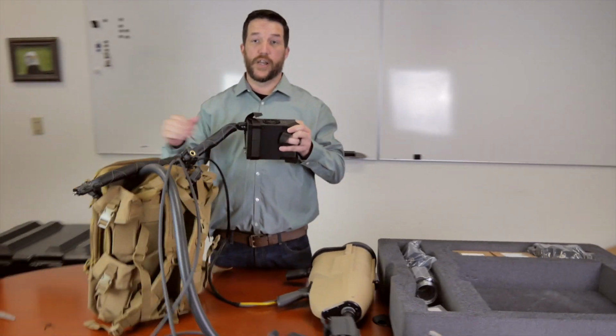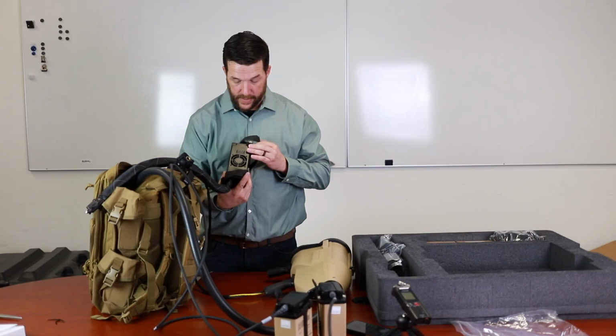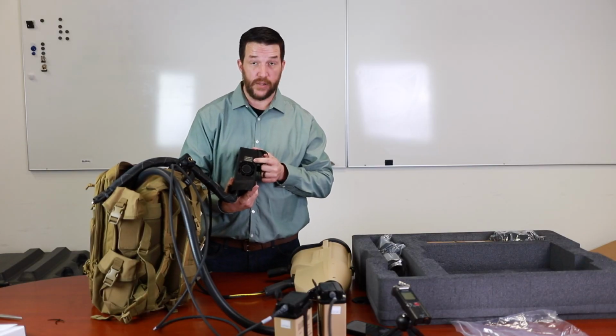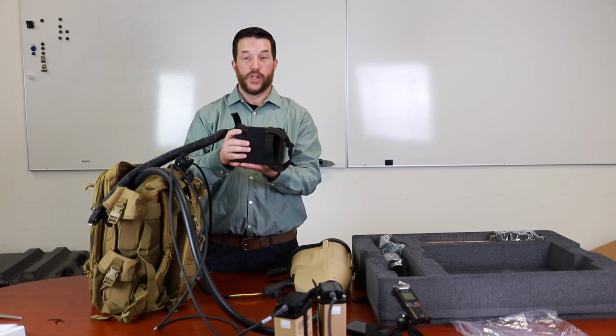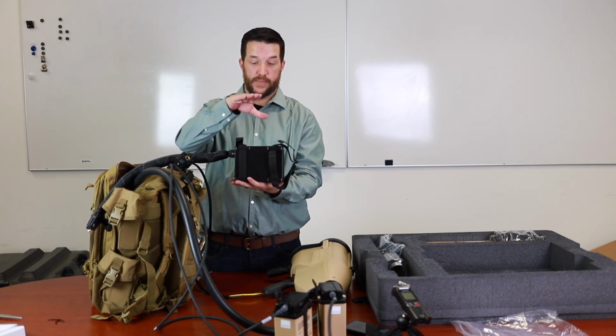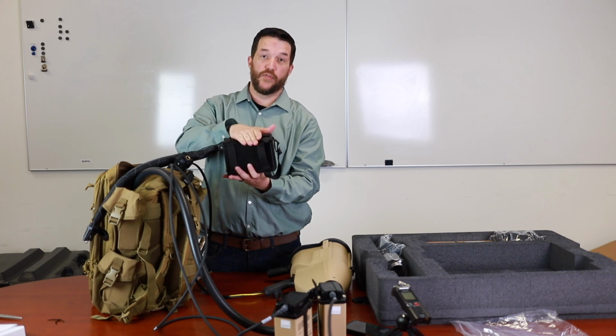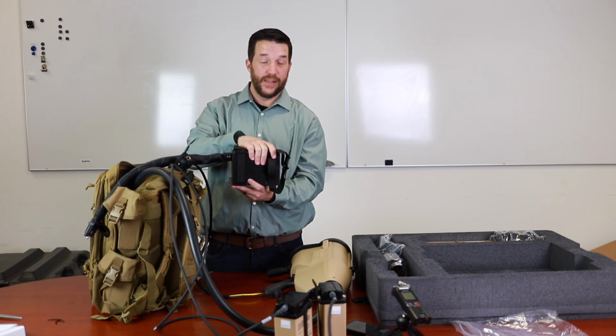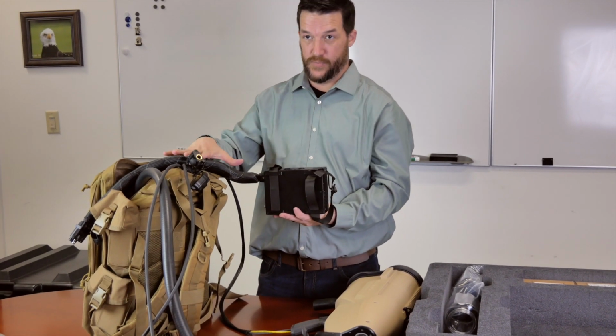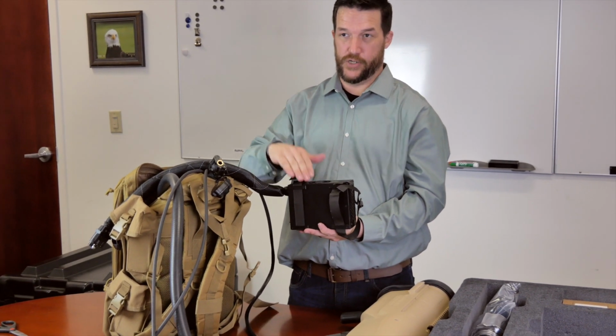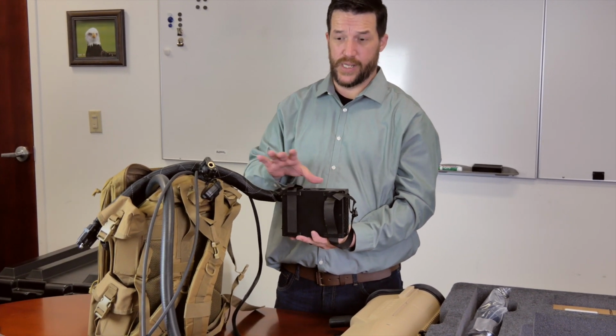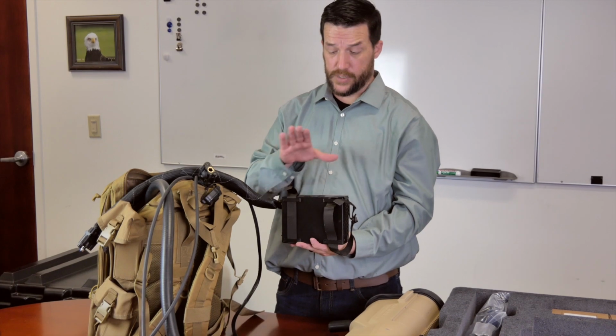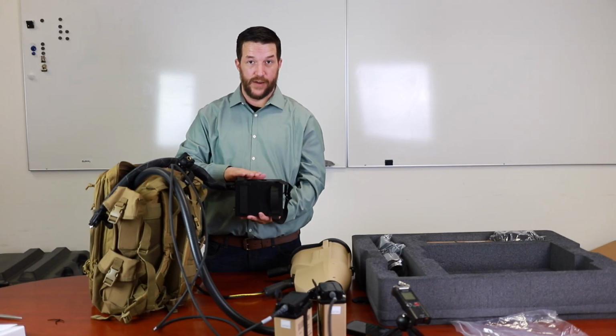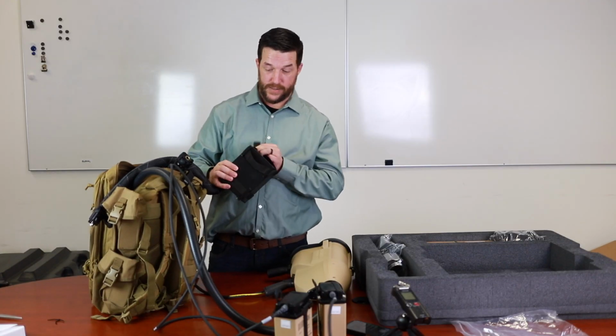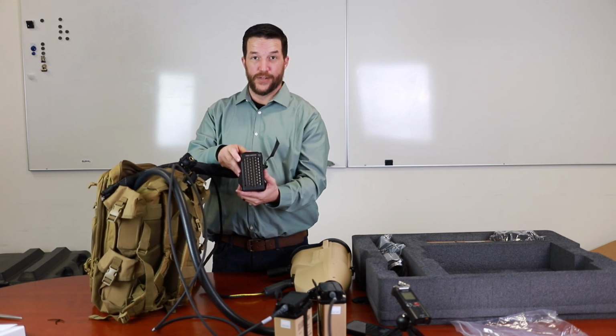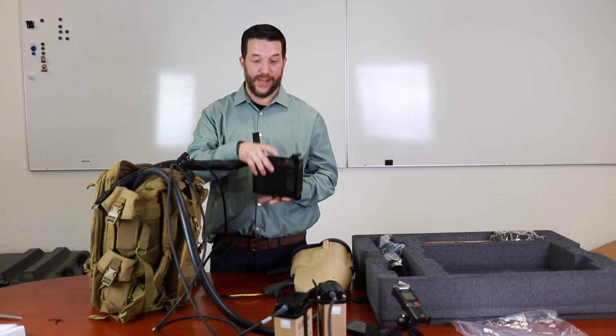Special care on the chiller on how you place it. You'll notice the safety in here. It says, so this side up, fan outlet do not block. Our chiller has to sit upright with this side being up. Any blockage of our fan, we will not be able to cool. Fan will not work, system will not cool, system will overheat and shut down. Very important that we keep this unobstructed from any obstacles up and nothing covering our fan or intake. Air inlet, do not block. Do not block fan, keep it upright.